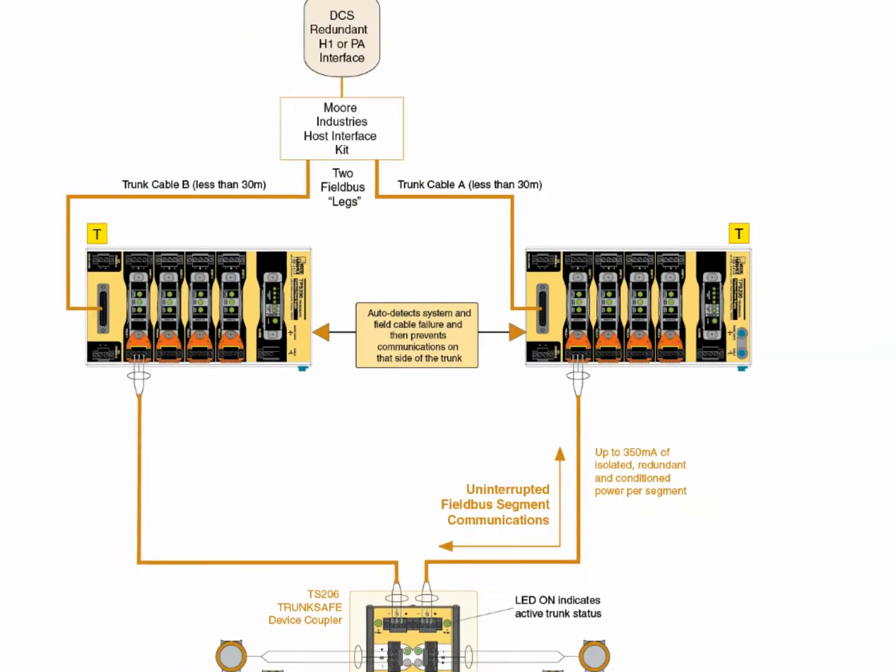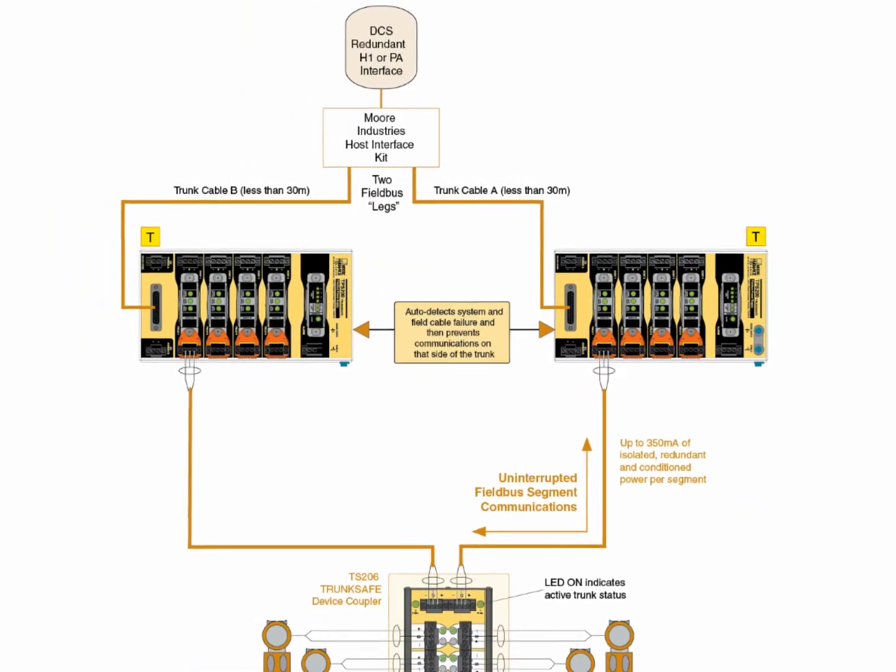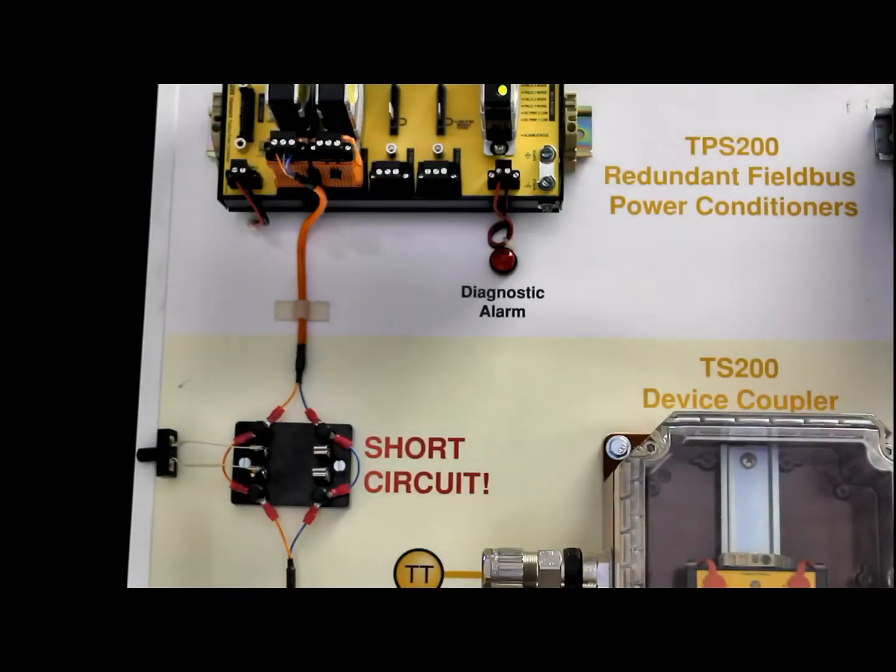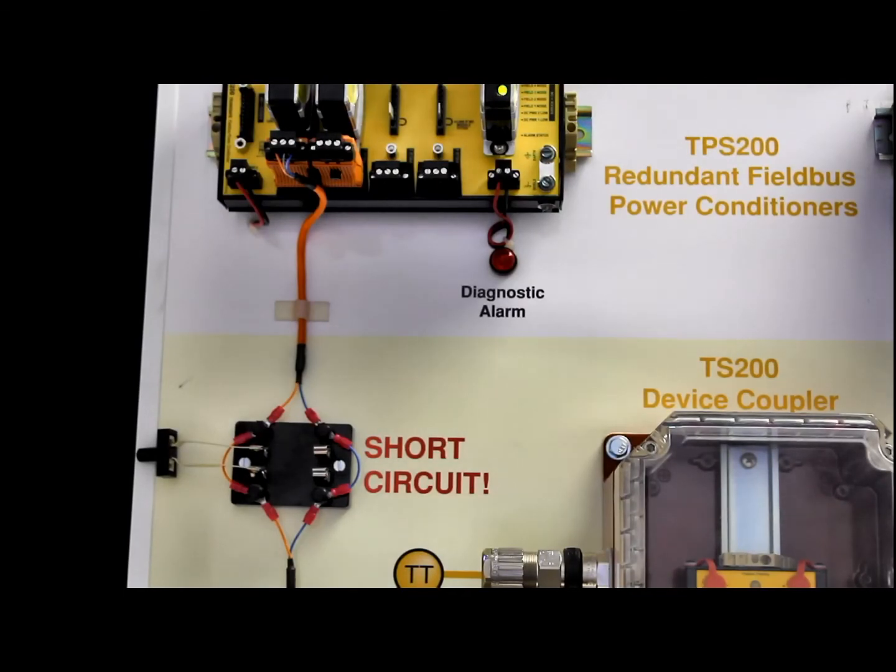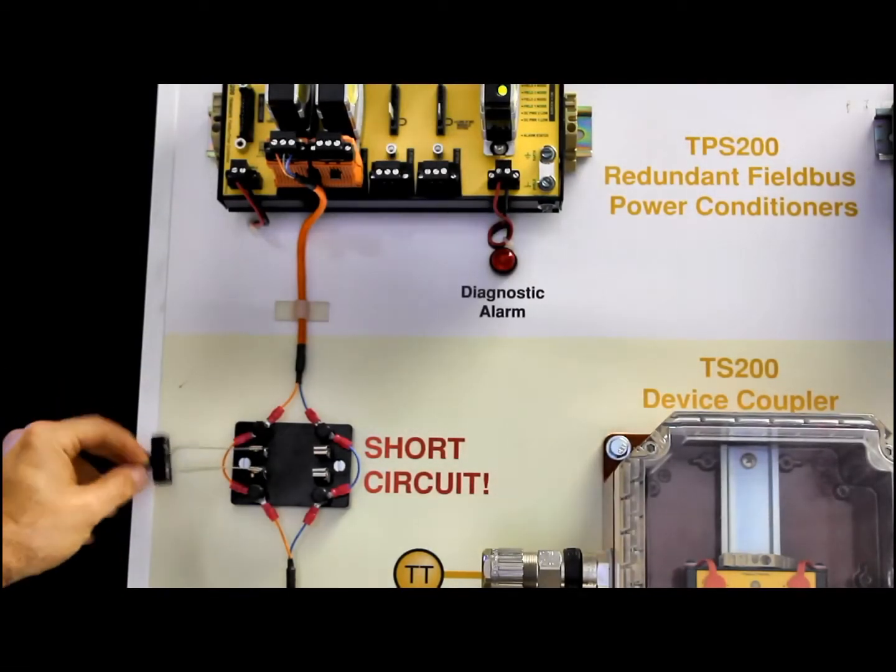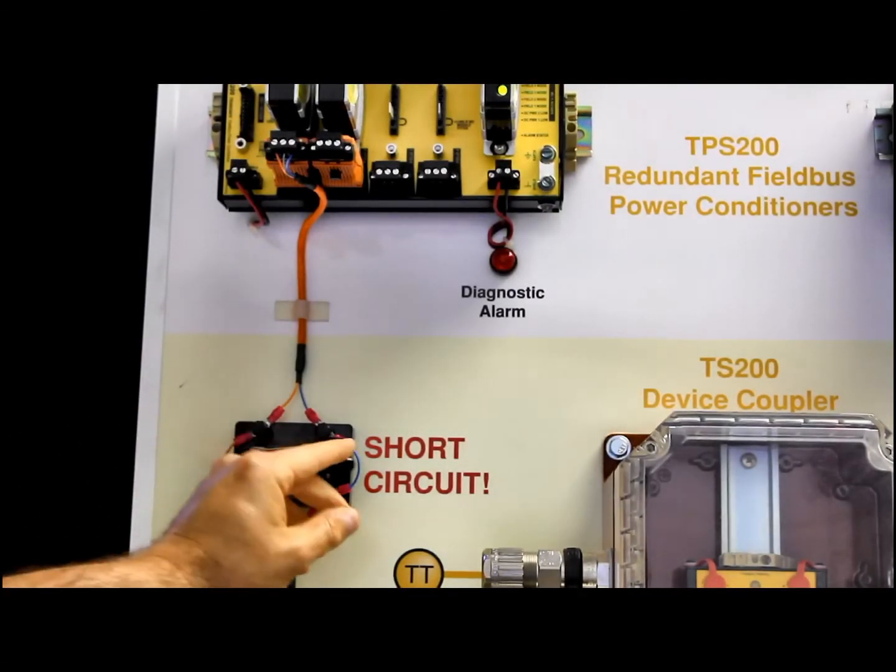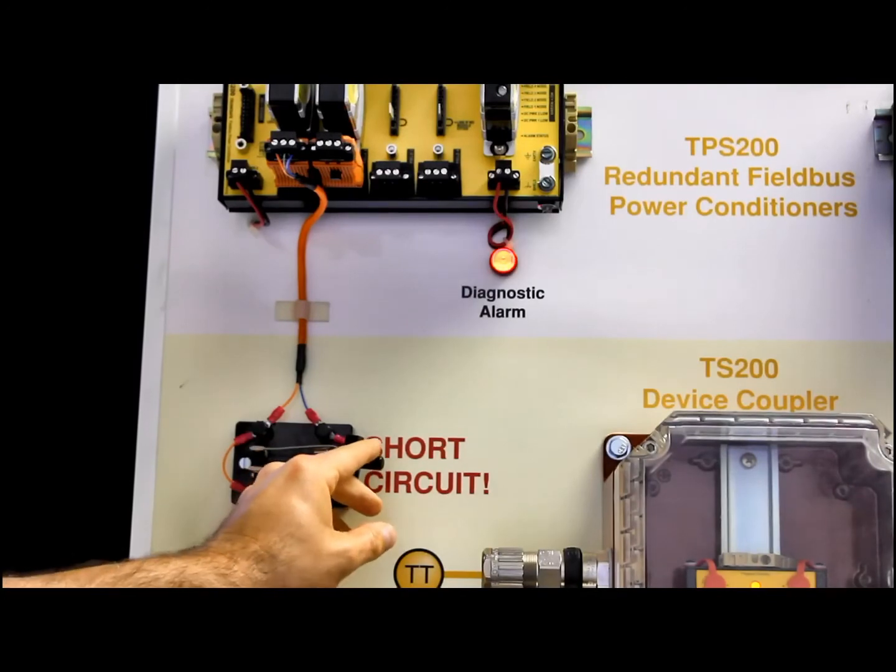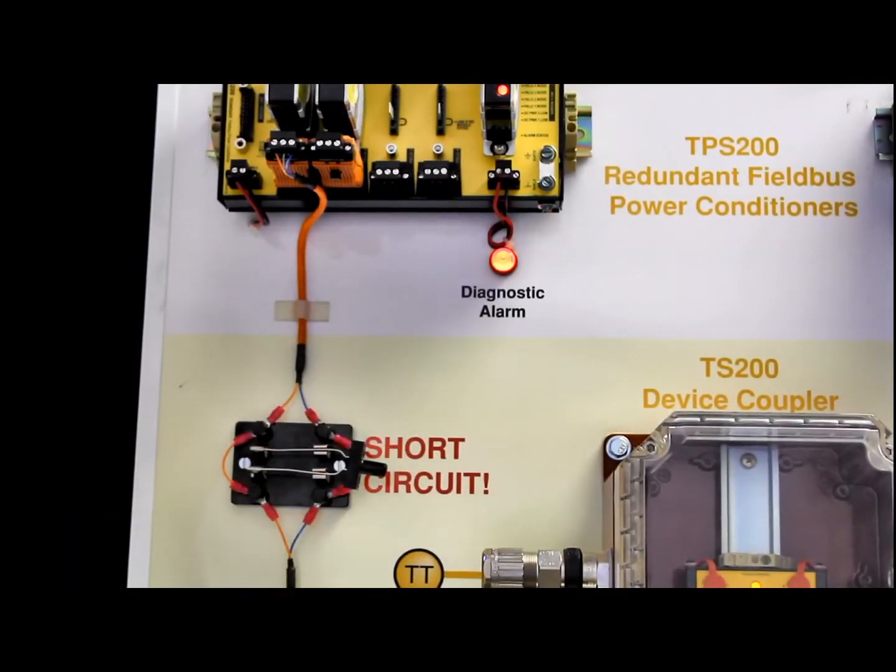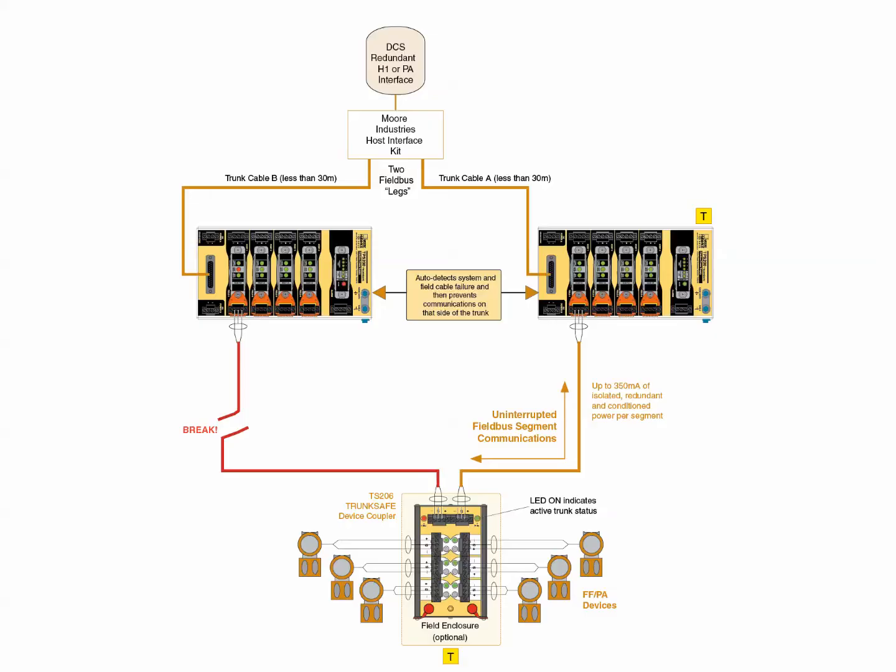In normal operations, power and communications exist on the entire segment until a fault is detected. Trunk Safe protects the field bus segment against single-point failures, which are most often caused by trunk cable short circuits, breaks, or inadvertent trunk disconnections by plant personnel, which cause segment open circuits.